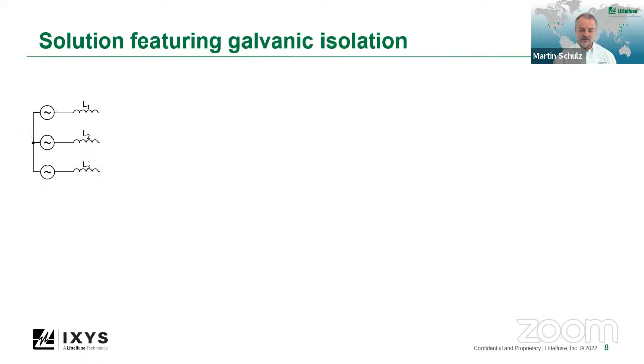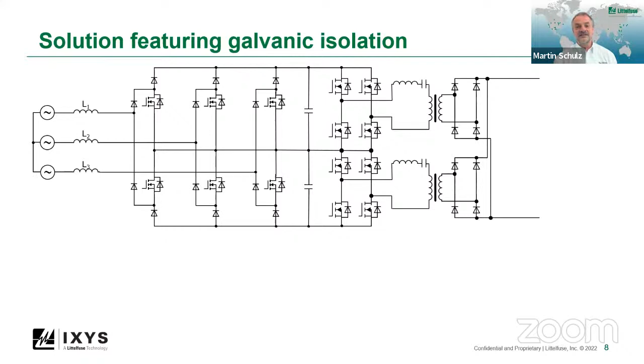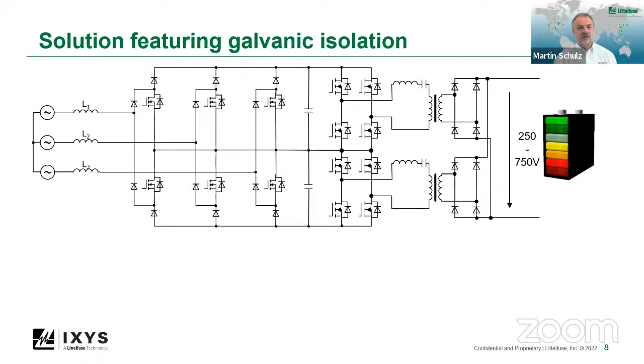So let's take a look into the solutions for that feature, galvanic isolation. There's always a three-phase grid because from a single phase, you're not going to get those hundreds of kilowatts. There's an input rectifier. In this stage, it's just a different drawing of a Vienna rectifier. And this one provides power to a DC link that in turn provides the AC to drive a series connected or parallel connected LLC stage. And then the battery is driven with up to 250, up to 750 volts, which is one of the limitations in this setup. A three-phase input with a Vienna rectifier is one solution.